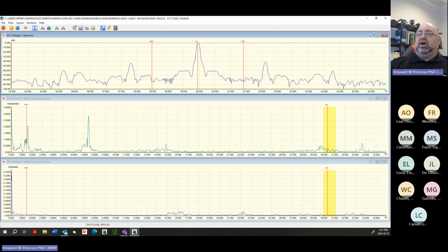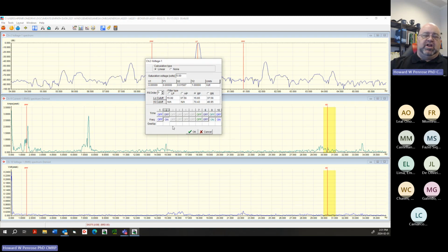If I needed to do a more serious change, you would have to go into here and you would literally have to start changing numbers in here. And don't do that unless there's something very specific we need to do. So for instance, if you had things set up incorrectly, say you had 1 millivolt per amp in one and you had 10 in the other two, and you meant to make it 10 on each one, you would go to the other channel and you would select the X, copy that, go back to the first channel, paste it in there. You have now changed the actual data set. It will go back through and recalculate everything. So you don't want to do that unless you have to.